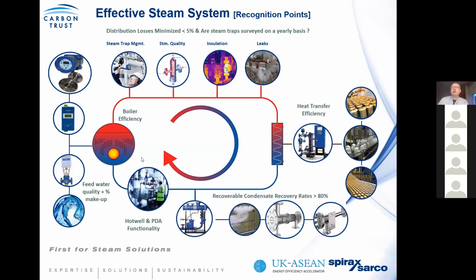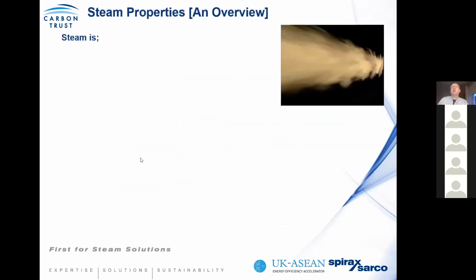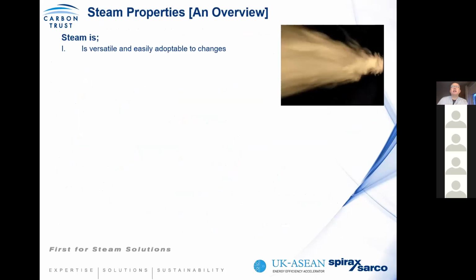And then, importantly, we look at your condensate recovery, or what we call your recoverable condensates, because within the food and beverage sector, some of the steam can be used directly within the process itself. However, what's important, as mentioned in the introduction, is that conducting and maintaining an efficient steam system is not a once-off process. It's a continuous process, and you need to continually re-look at the systems to see where current and future savings can be achieved. So when we talk about steam, what are we talking about? Steam is very versatile and easily adaptable to changes.